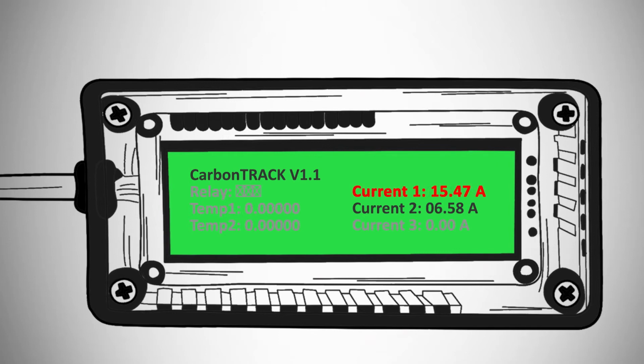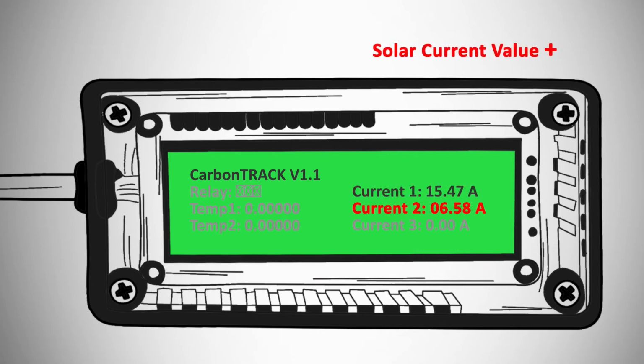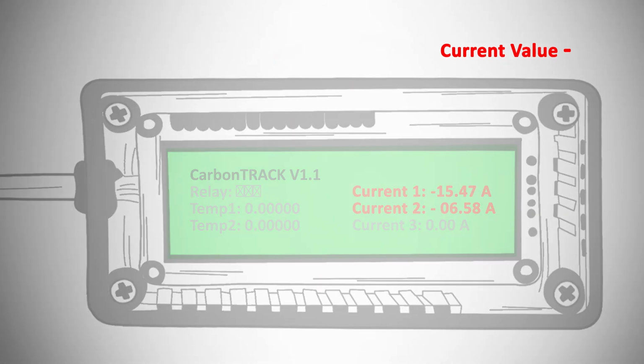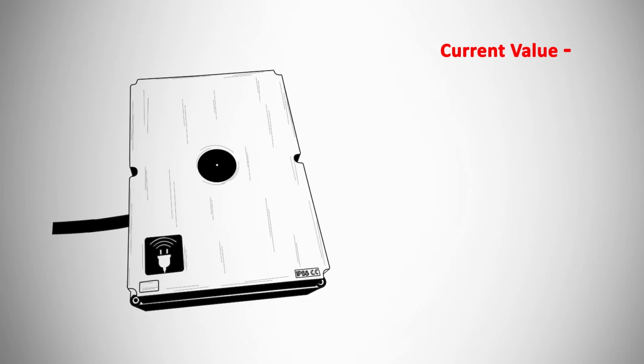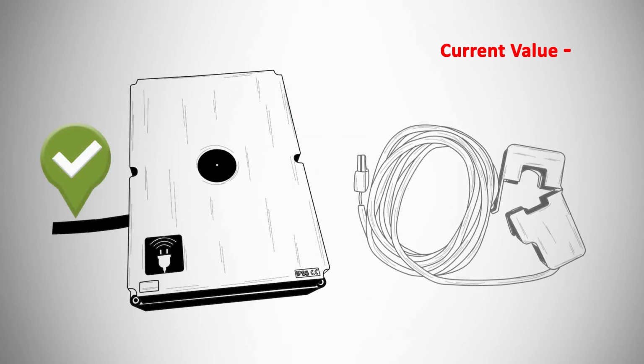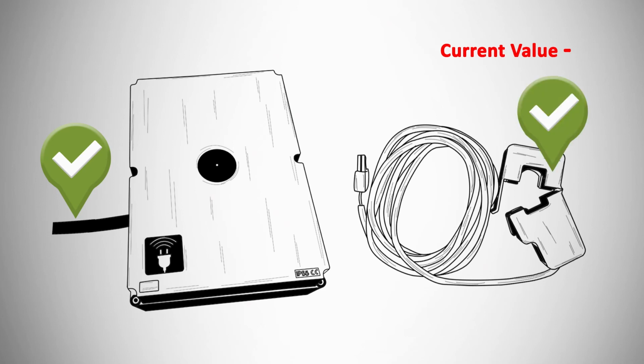In scenario 1, current 1 could be positive or negative depending on whether energy is being exported back to the grid. However, for scenario 2, current 1 should always be positive, corresponding to the current flowing from the mains. Current 2 should also show a positive value if the solar system is generating power. If current 1 or current 2 values are 0, check that the current clamps are connected properly to the CT unit. You may also need to check for current flowing through the line with an amp meter.